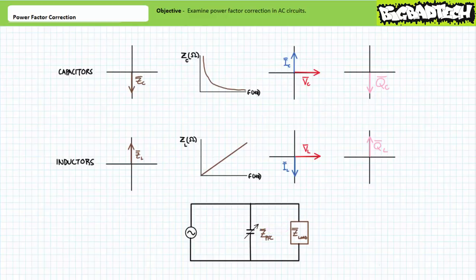It should be noted that most small-scale power factor correction scenarios involve the placement of a variable power factor correcting capacitor in parallel with an electrical load that exhibits inductive characteristics and not the other way around. The reason behind the regularity of this arrangement is that ordinarily the electrical load in question being power factor corrected is in fact a motor, which ordinarily exhibits inductive behavior.